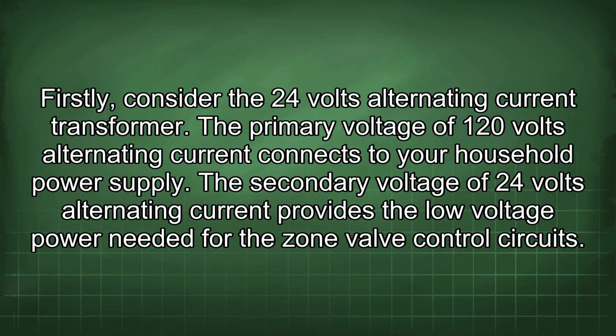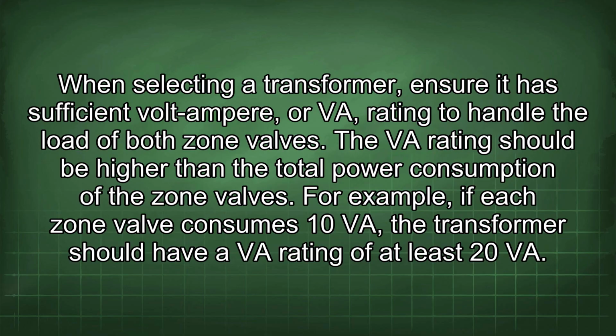Firstly, consider the 24 volts alternating current transformer. The primary voltage of 120 volts alternating current connects to your household power supply. The secondary voltage of 24 volts alternating current provides the low voltage power needed for the zone valve control circuits. When selecting a transformer, ensure it has sufficient volt-ampere or VA rating to handle the load of both zone valves. The VA rating should be higher than the total power consumption of the zone valves. For example, if each zone valve consumes 10 VA, the transformer should have a VA rating of at least 20 VA.